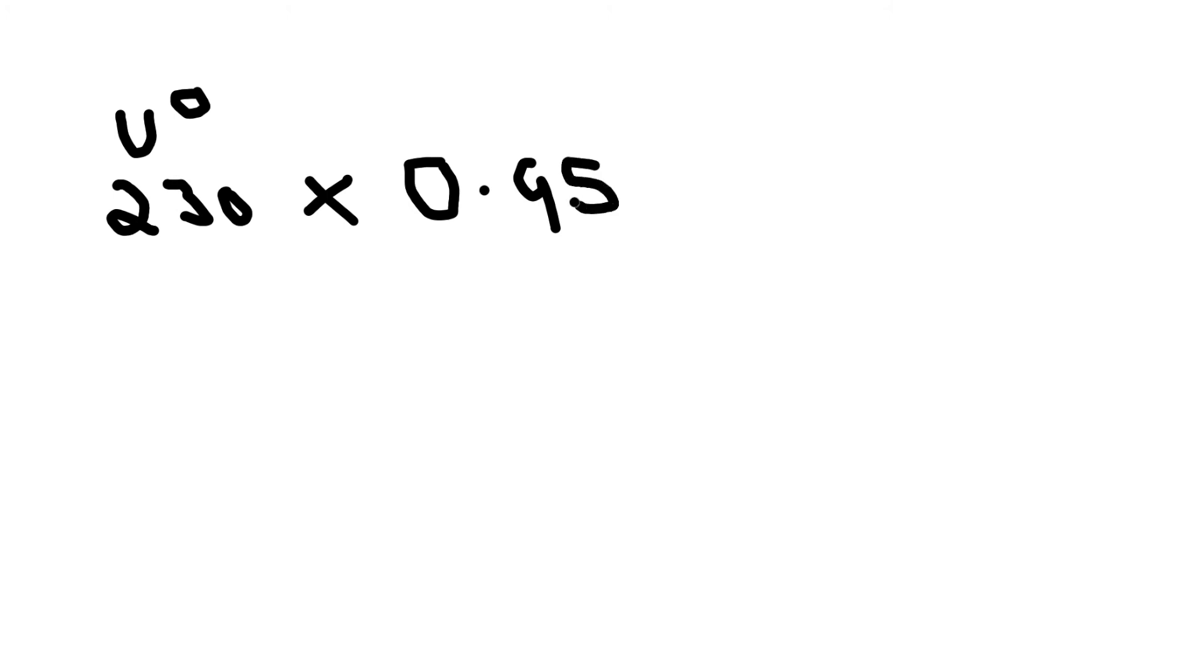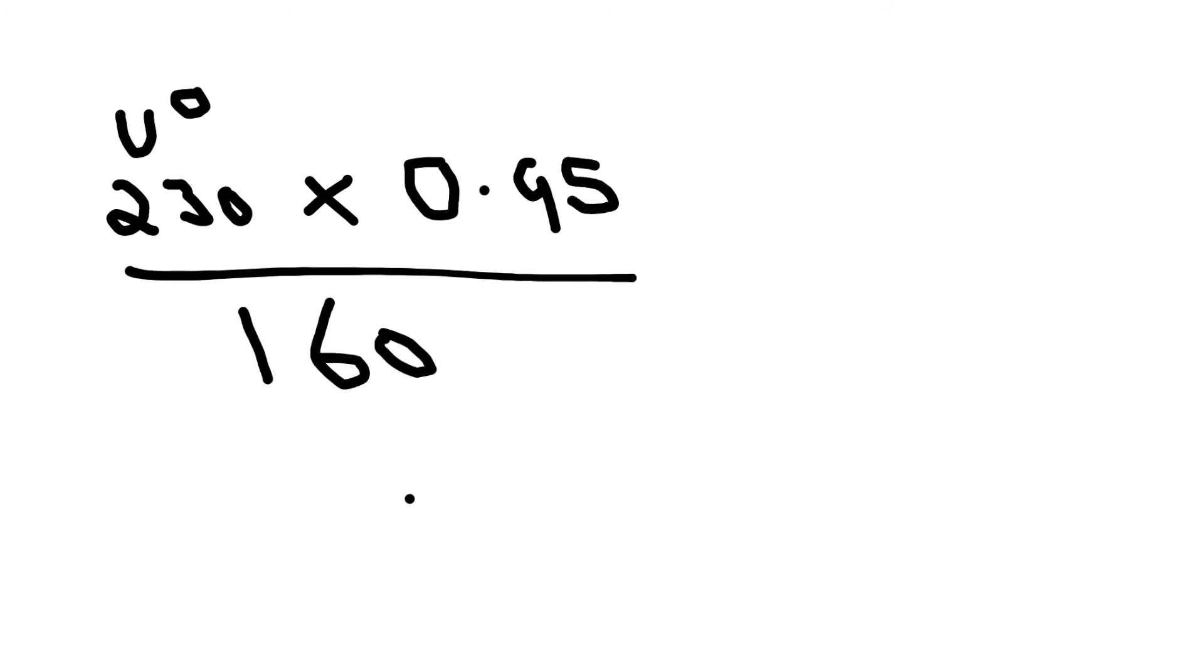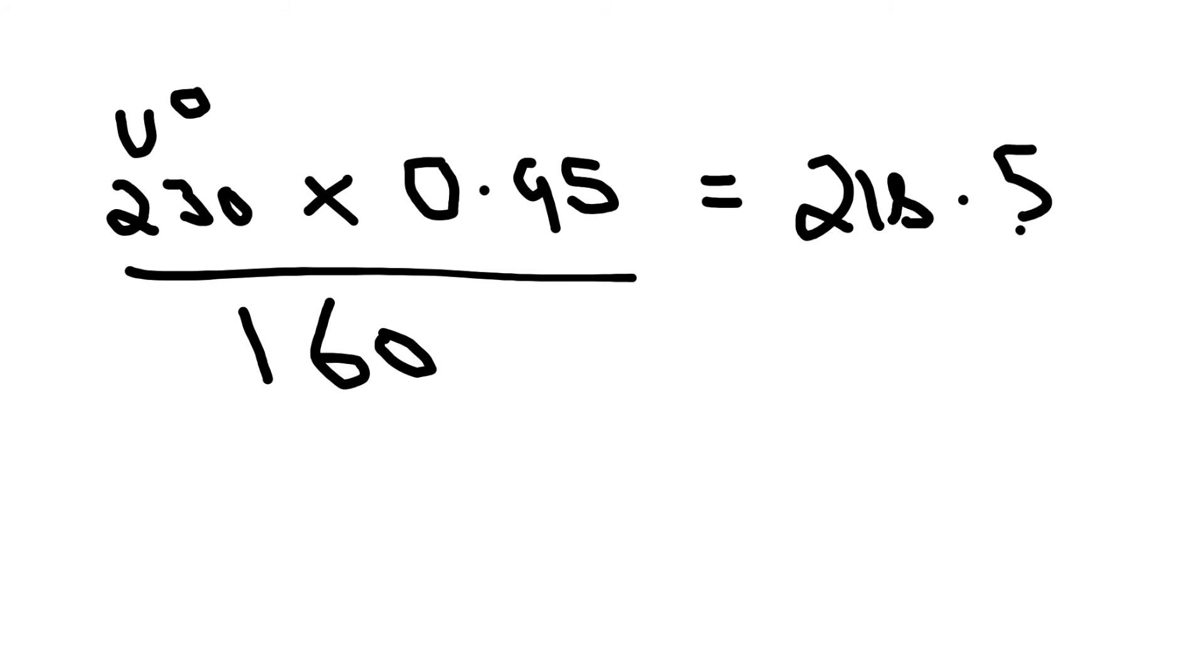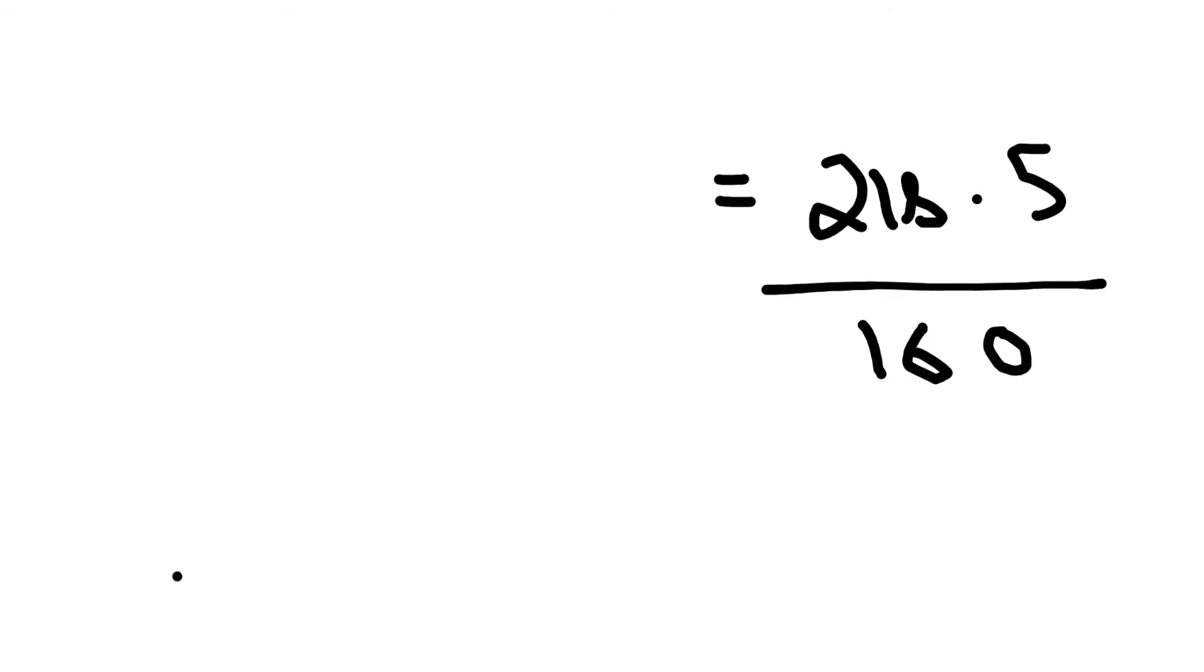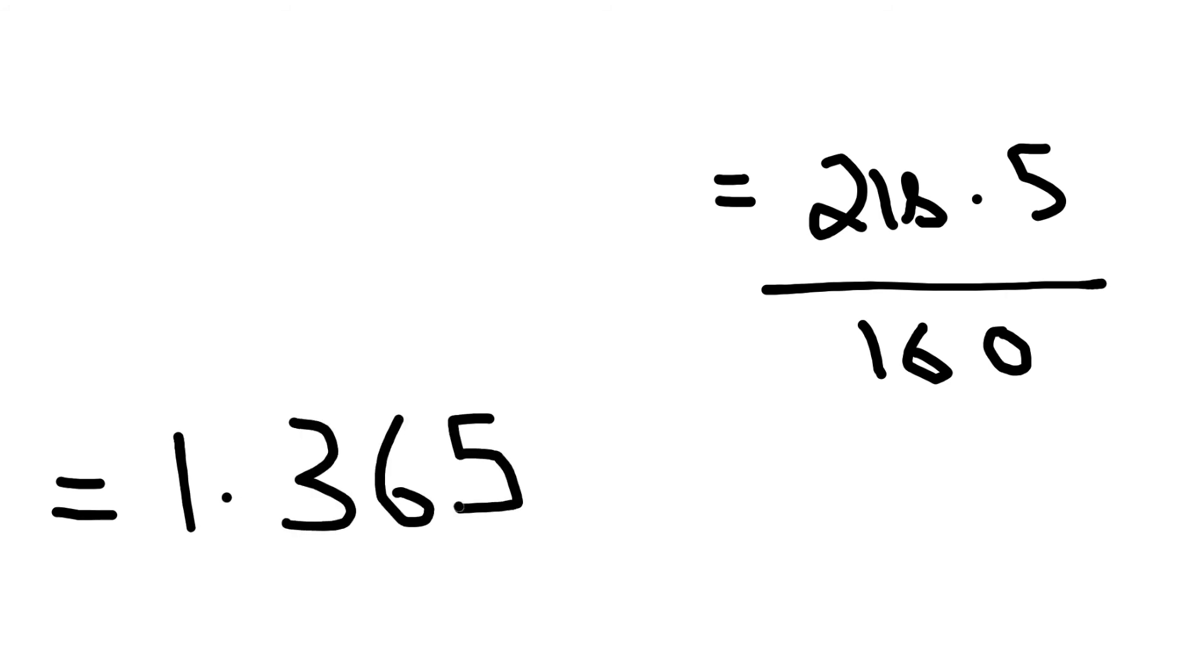So let's put this into something you can understand and break it right down. We've got UO which is 230, the nominal voltage line to earth, and we're timesing it by C-Min, that's 0.95, and you're dividing the whole thing by 160. If we do the top line first, that equals 218.5 divided by 160, and if you do the maths on that it comes out at 1.365.